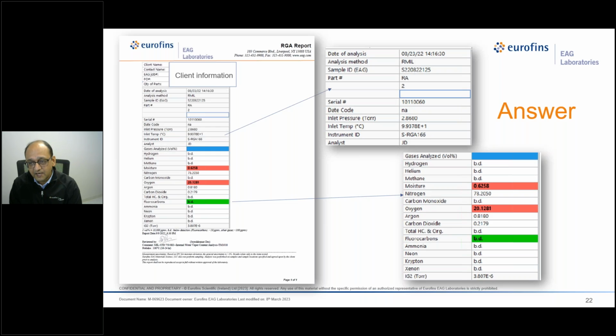There is no standard on that. Basically, the units are changed. When we are talking about a very small amount of gas, we should be talking in ppm, whereas a higher amount of gas could be said in volume percentage. For example, oxygen here is almost 200,000 ppm, which makes sense, but it's not very usual to say. So we say 20 volume percent of the gas, but here we could say 6,000 ppm of moisture. So it's a convenience, but there is no difference between volume percent and ppmv, and that's why we put that information at the bottom of the report.